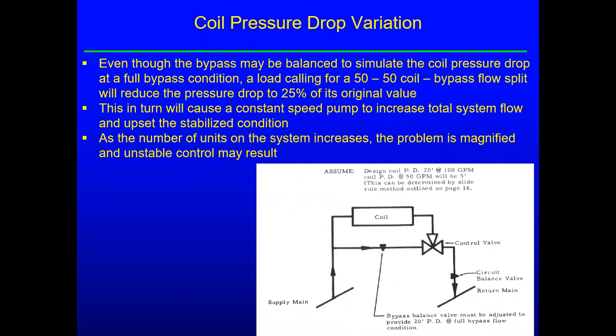So even though the bypass may be balanced to simulate the coil pressure drop at the full bypass condition, a load calling for 50% through the coil and 50% through the bypass will reduce the pressure drop to 25% of its original value. This in turn will cause the constant speed pump to increase total system flow and upset a stabilized condition. And so as the number of units on the system increases, problems are magnified. Now, again, with variable speed pumping, you can alleviate this.